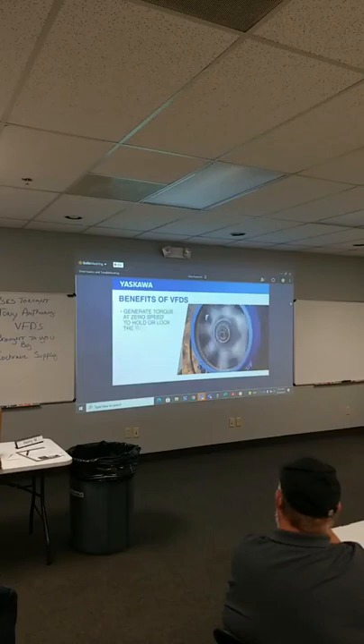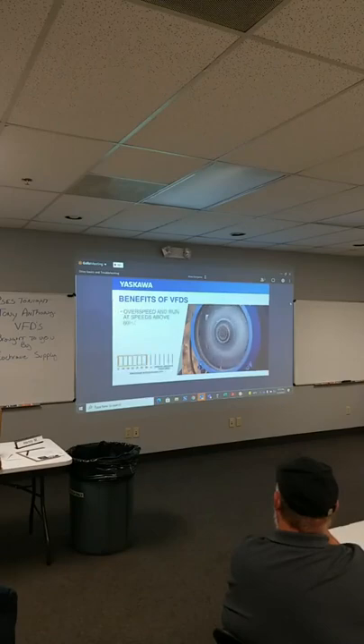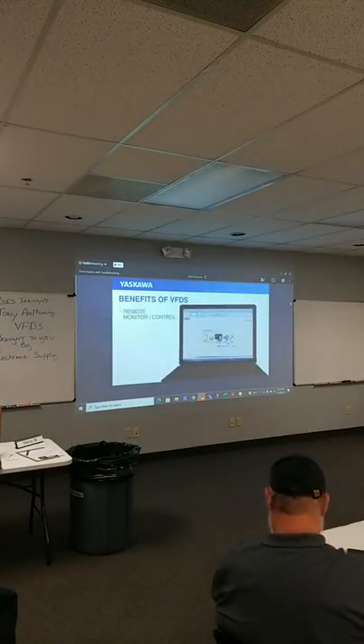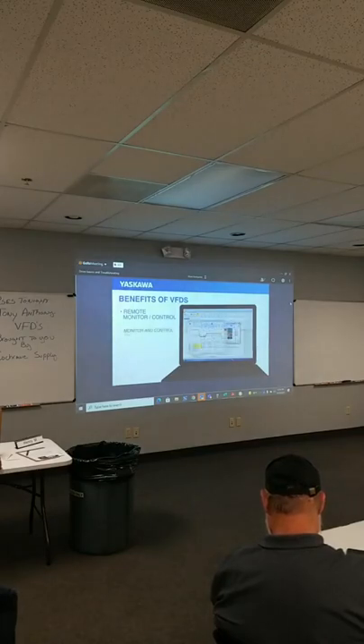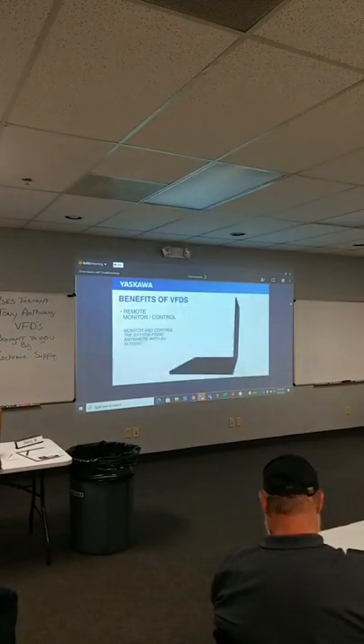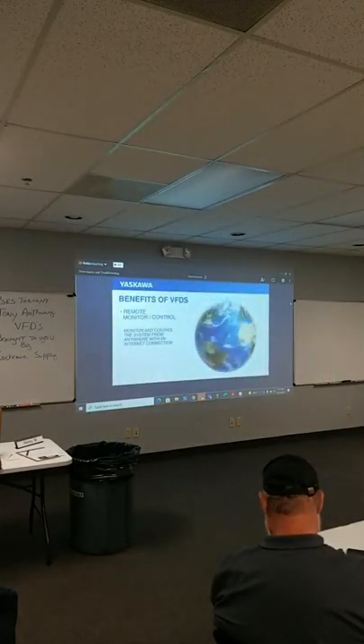We can generate torque at zero speed, hold or lock the rotor, a feature previously limited to servos and mechanical brakes. On the other side of the table, we can now overspeed and run at speeds above 60 hertz, provided the motor is able to accommodate that speed. Remote monitor control means that you can monitor and control the system from your desk or from anywhere in the world where you have an internet connection.